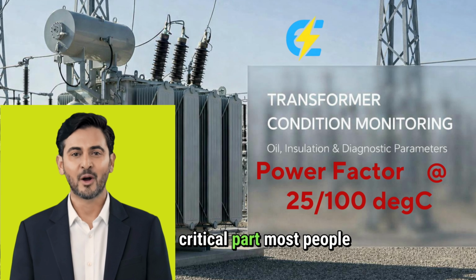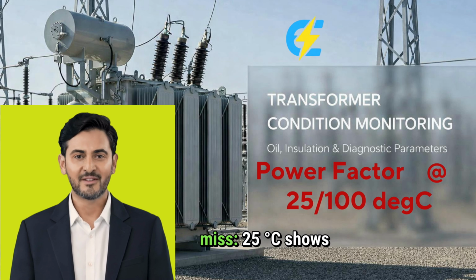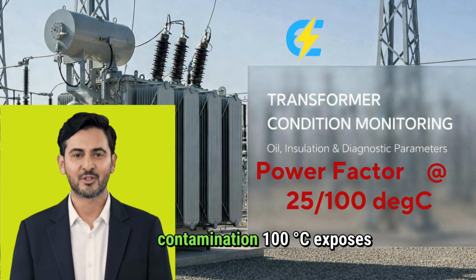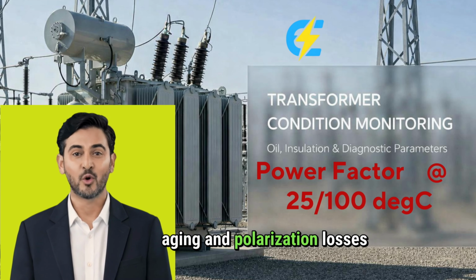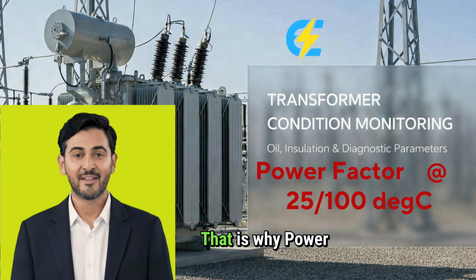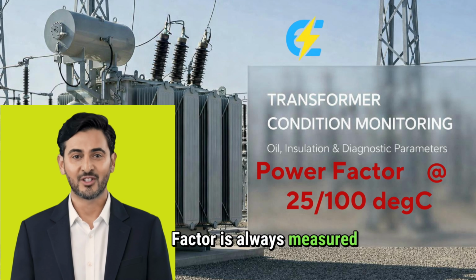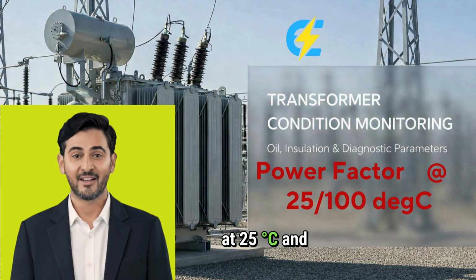And here is the critical part. Most people miss: 25-degree Celsius shows contamination. 100-degree Celsius exposes aging and polarization losses. That is why power factor is always measured at 2 temperatures. A transformer may pass at 25-degree Celsius and fail badly at 100-degree Celsius.